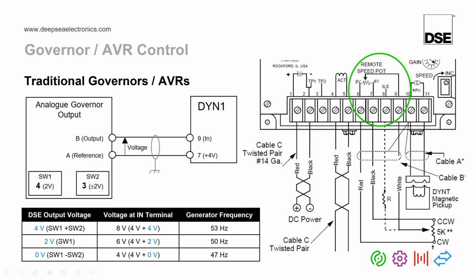And then you can see, if we want to increase or decrease speed, the DSE module adds or subtracts more voltage. In this case, we have a switch 2 setting of 3 plus or minus 2 volts. So for the DSE module to ask the generator to run at 53 hertz in this example, it will go to 4 volts, which is switch 1, 2 volts, plus switch 2, 2 volts. And if we wanted it to run at 47 hertz, we'd ask the DSE module to produce 0 volts, which in this case is switch 1, again 2 volts, but this time minus switch 2, 2 volts.